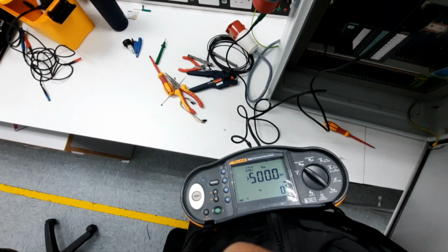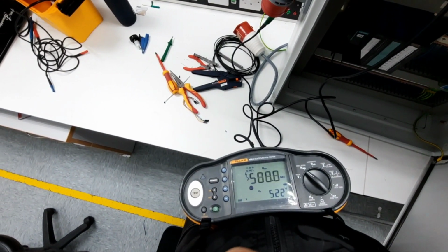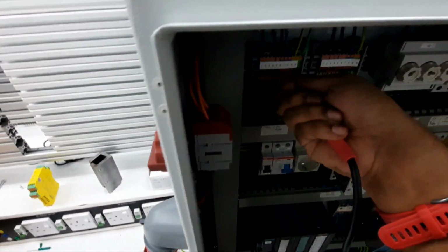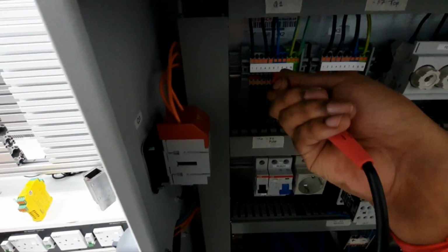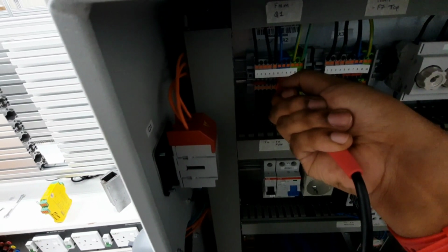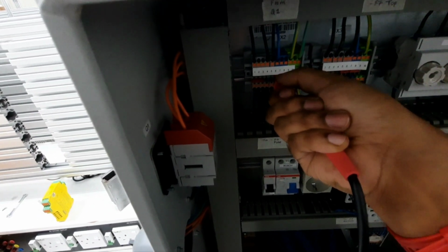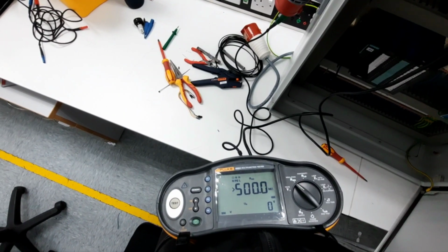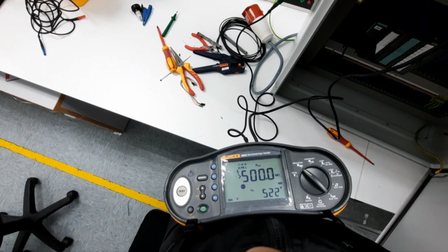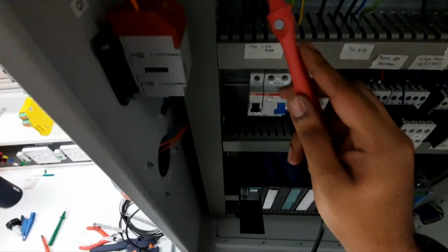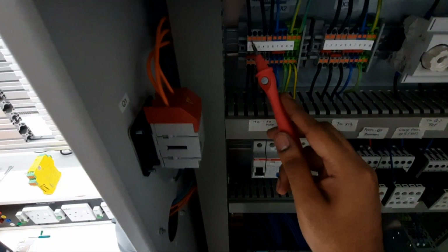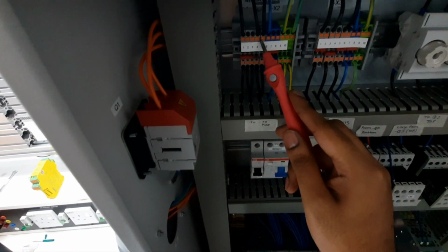Then again, and last but not least, neutral. It'll be 500 - let me do that again. So remember, for the insulation test it's line 1, line 2, line 3, and neutral.